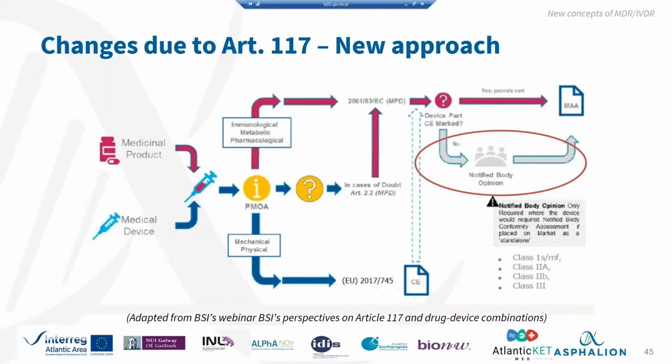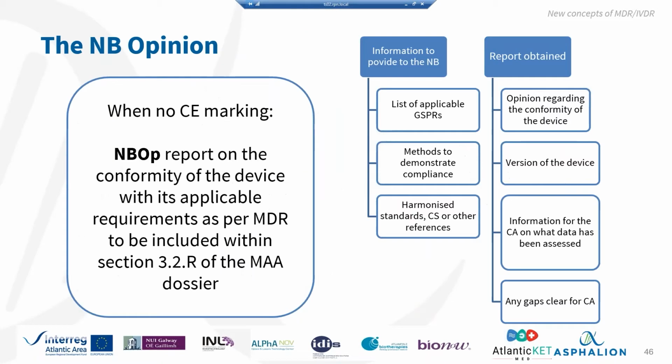Okay. So this report, this notified body opinion, as we said, is a report that has to be in place when the device has no CE marking. What you will have to send to the notified body is the list of the general safety and performance requirements applicable to your device, the methods to demonstrate compliance with these requirements, and then you also have to send the harmonized standards or common specifications or references that you are going to use to demonstrate compliance.